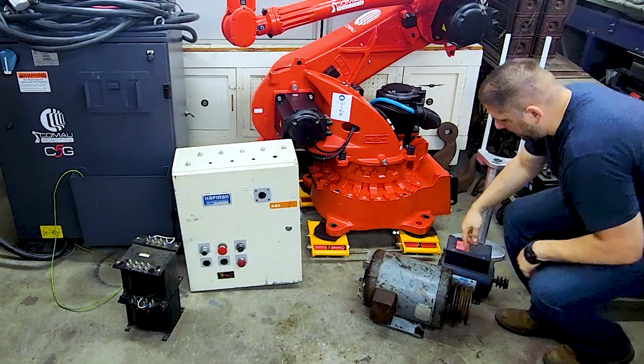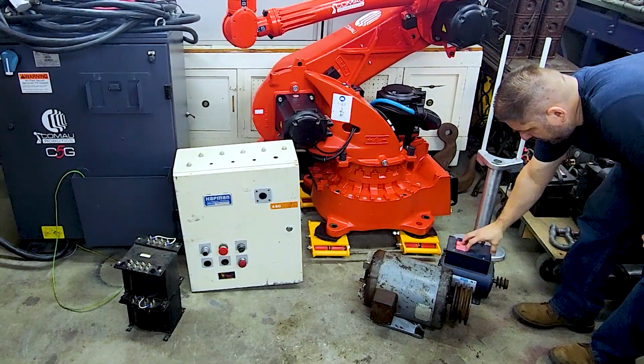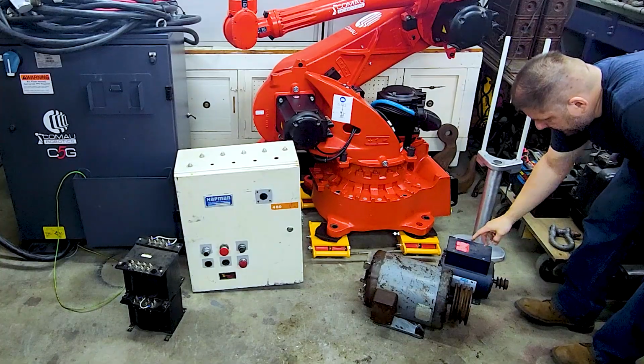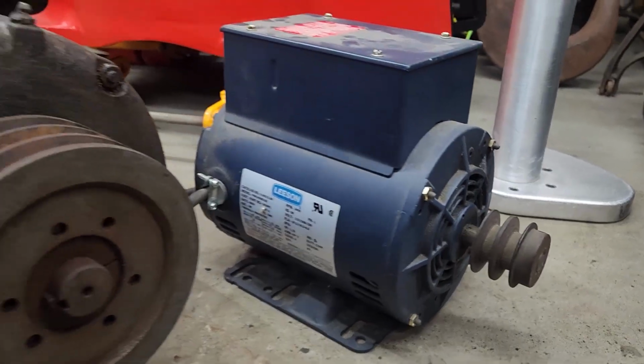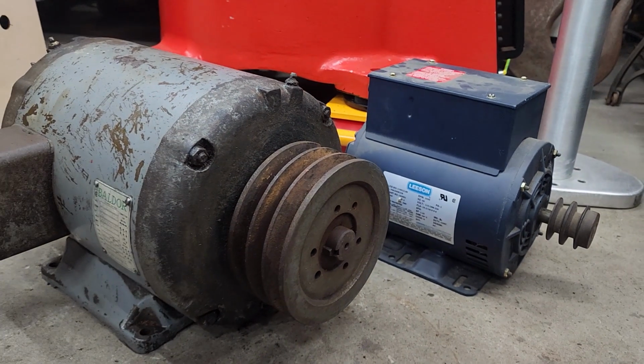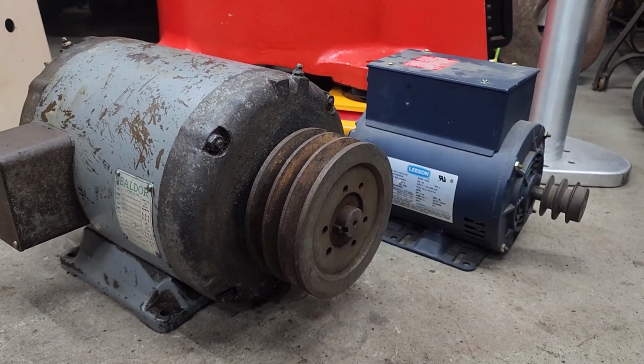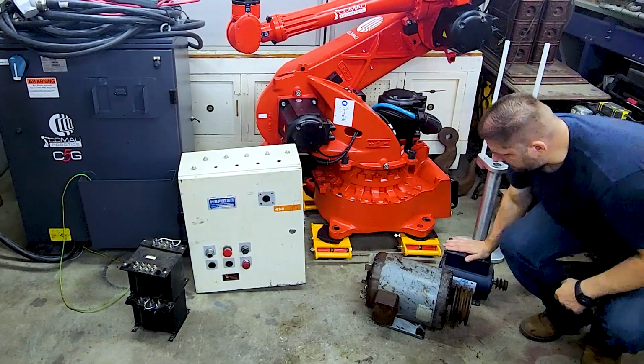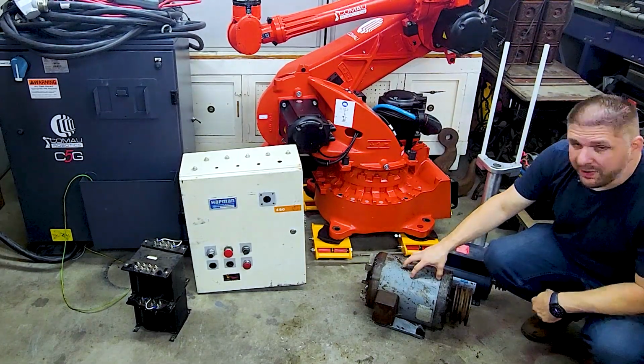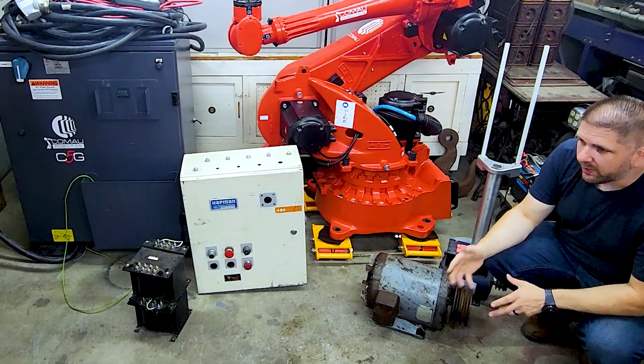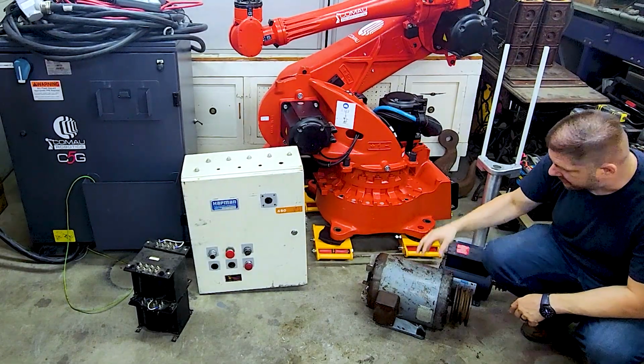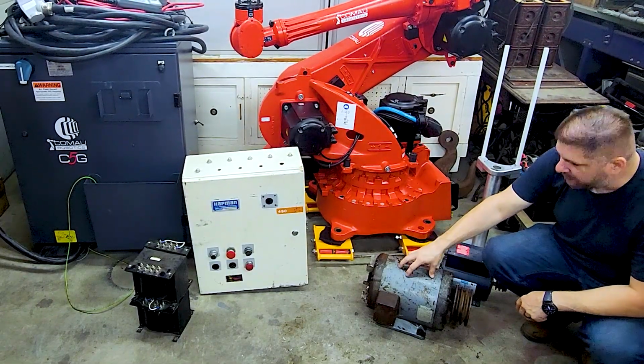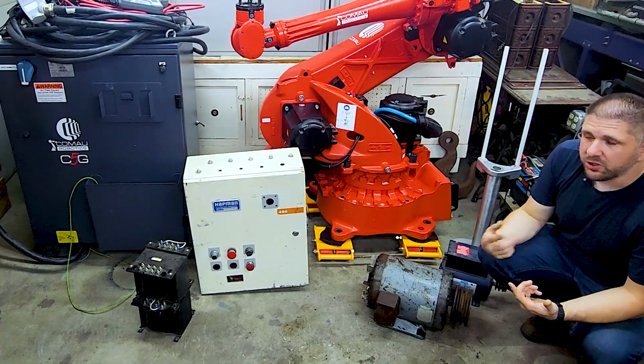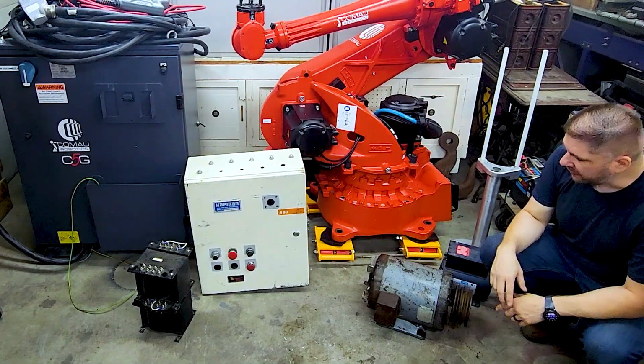Why I have this other motor back here behind it: this is a 120 volt, 2 horsepower motor. This is like an 1800 RPM motor with a gear reduction to be able to ramp this motor up. This is called a pony motor. So this motor will be used to spin up this bigger motor because I don't have run caps that are rated for 460 volts or start caps to start this guy up. So this will spin it up to speed, which also gives me a lower starting torque instead of a big inrush of current whenever this is starting up.